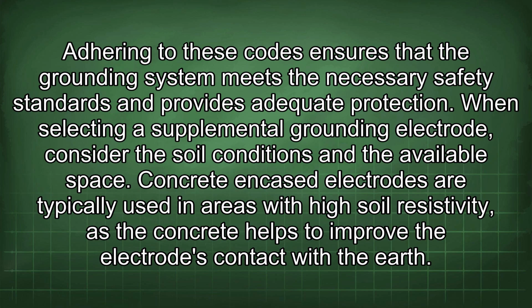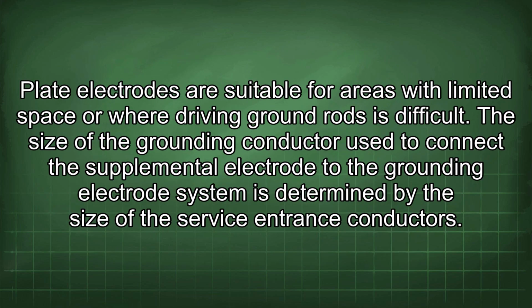When selecting a supplemental grounding electrode, consider the soil conditions and the available space. Concrete encased electrodes are typically used in areas with high soil resistivity, as the concrete helps to improve the electrode's contact with the earth. Plate electrodes are suitable for areas with limited space or where driving ground rods is difficult.